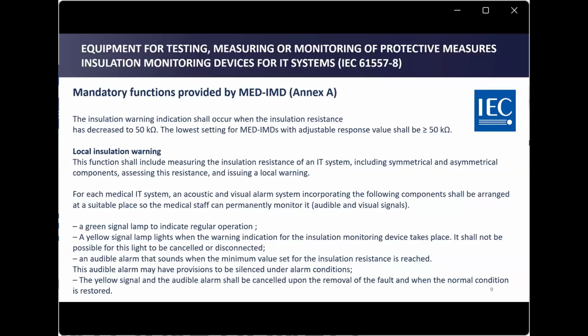What are mandatory functions provided by MED-IMD? The insulation warning indication shall take place at the latest when the insulation resistance has decreased to 50 kiloohms. For MED-IMDs with adjustable response value, the lowest setting shall be over 50 kiloohms. Local insulation warning has to be there. This function shall include the measurement of the insulation resistance of an IT system, including symmetrical and asymmetrical components, and assessment of this resistance and local warning.